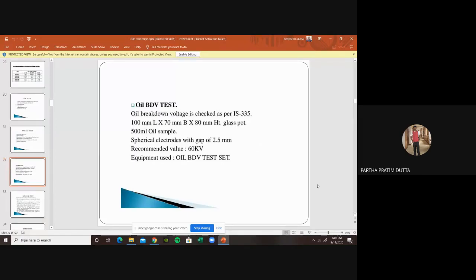Then I'll go for the oil BDV test I have told you, the oil breakdown voltage for insulating oil. This is as per IS standard 335. We take a glass pot of 100 mm length, 70 mm breadth, and 80 mm height. We collect a 500 ml oil sample from the transformer, put in spherical electrodes with a gap of 2.5 millimeter, and apply voltage to the electrodes, usually 60 kV. If it withstands the oil BDV test, we say the oil is good. If the oil breaks down below 45 kV, we say the oil is contaminated, for reclamation, refining or change of the oil.